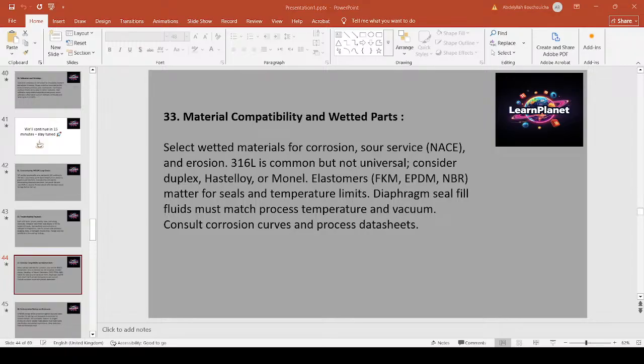Select wetted materials for corrosion resistance, service, and erosion. 316L is common but not always suitable. Elastomers have different chemical and temperature limits. Match them to process fluids and ambient conditions. Diaphragm seal fill fluids must suit operating temperature and any vacuum conditions to avoid vaporization. Consult chemical compatibility charts and datasheets for long-term reliability. Example: for chlorinated process stream, select the Hastelloy diaphragm and PTFE-faced elastomer seals.